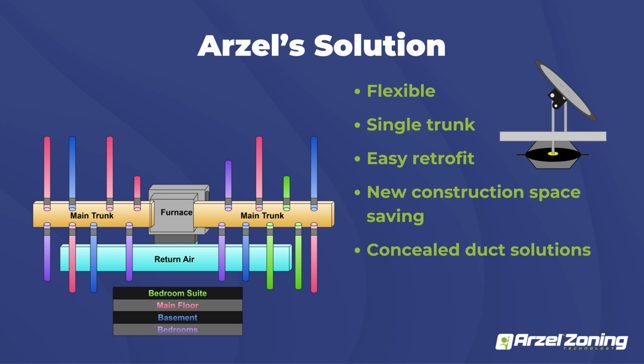But one of the things that Arzel really strives at is our retrofit dampers and being able to zone an existing home without having to do drastic ductwork modification. So you guys are actually able to take our dampers and zone off each individual heat run in that home. So we would actually do branch style dampers. And as any of these panels ship, you'd be able to do up to 35 dampers on that panel. If you ever have a case where you're going to need more dampers than that 35, we can build you a custom panel, and that would be able to do up to 70 dampers on that job.